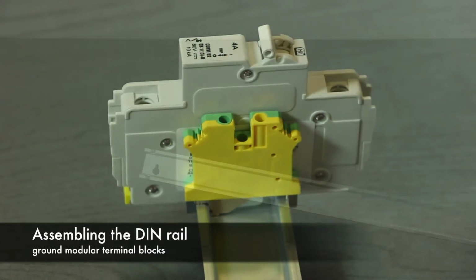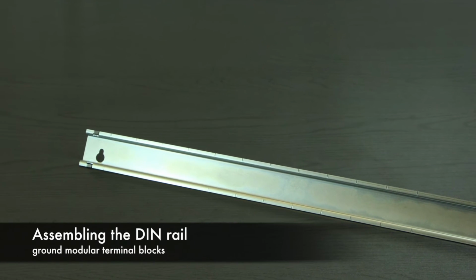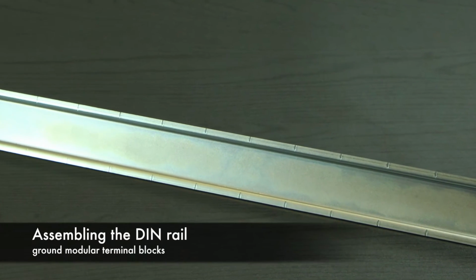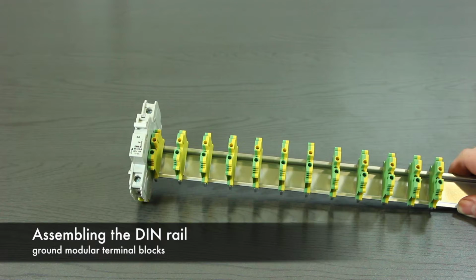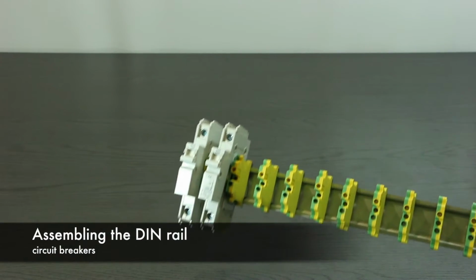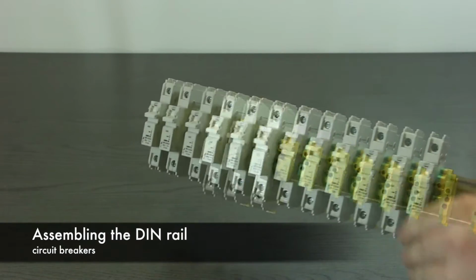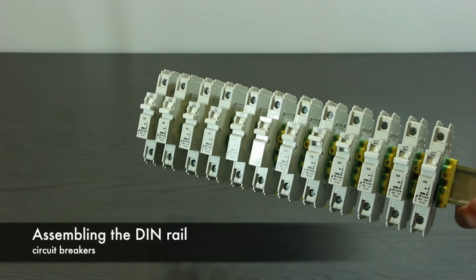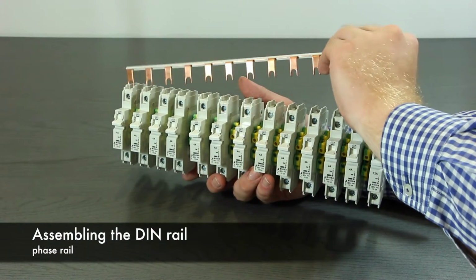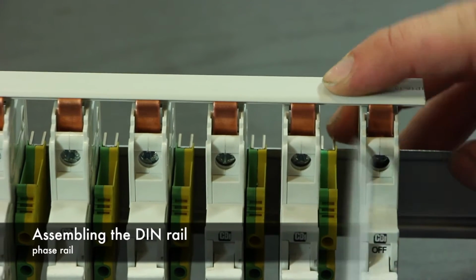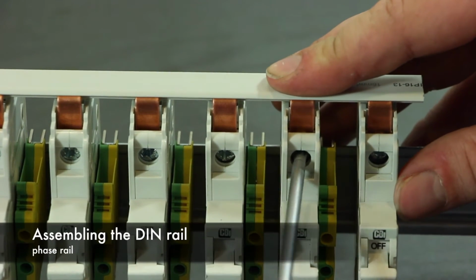Now mount the remaining terminal blocks to the right of the grooved markings on the DIN rail without any clearance to the marking and tighten them. Insert and lock the remaining circuit breakers to the left of each terminal block without any clearance. Connect the output of the circuit breakers using the phase rail and lock the corresponding screws. Don't forget to check the connection for tightness.